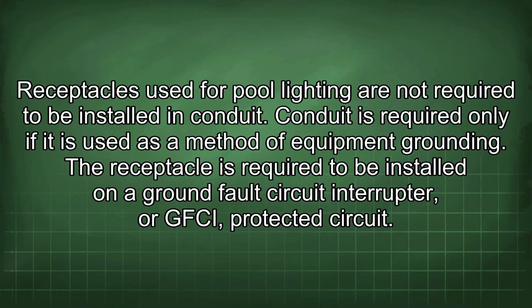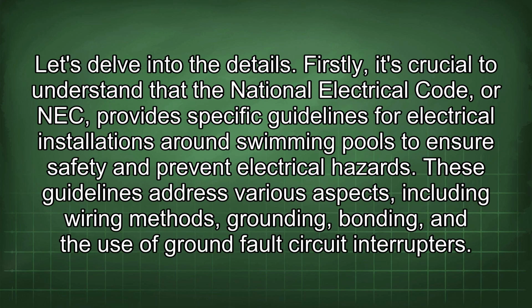Receptacles used for pool lighting are not required to be installed in conduit. Conduit is required only if it is used as a method of equipment grounding. The receptacle is required to be installed on a ground fault circuit interrupter, or GFCI, protected circuit. Let's delve into the details.